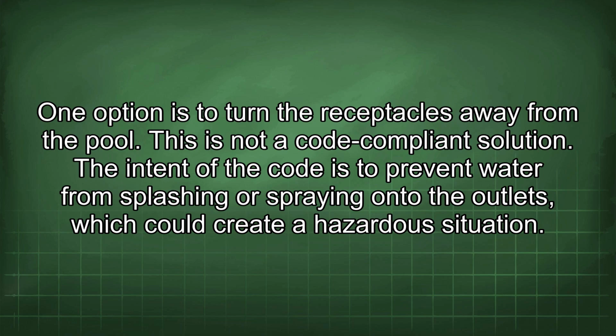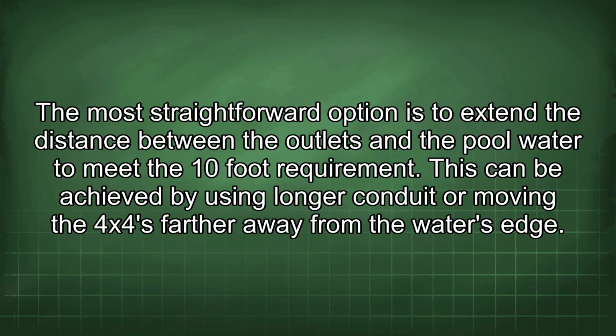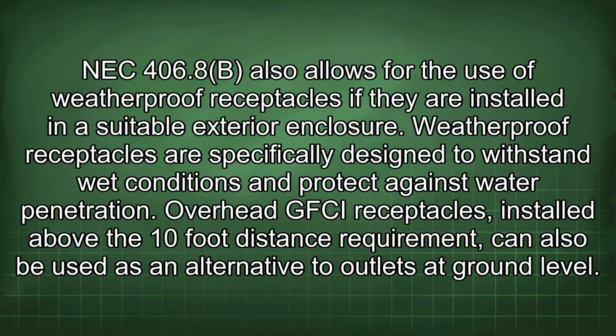The intent of the code is to prevent water from splashing or spraying onto the outlets, which could create a hazardous situation. The most straightforward option is to extend the distance between the outlets and the pool water to meet the 10-foot requirement. This can be achieved by using longer conduit or moving the outlets farther away from the water's edge. NEC 406.8b also allows for the use of weatherproof receptacles if they are installed in a suitable exterior enclosure.